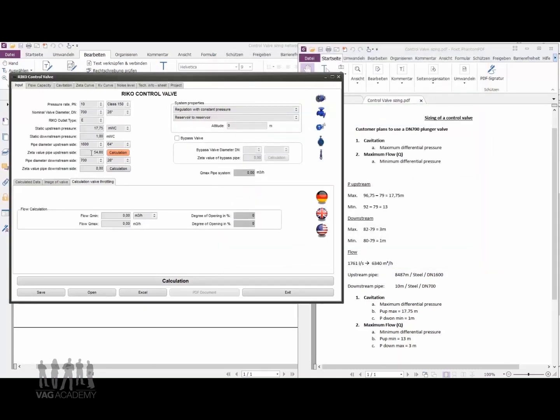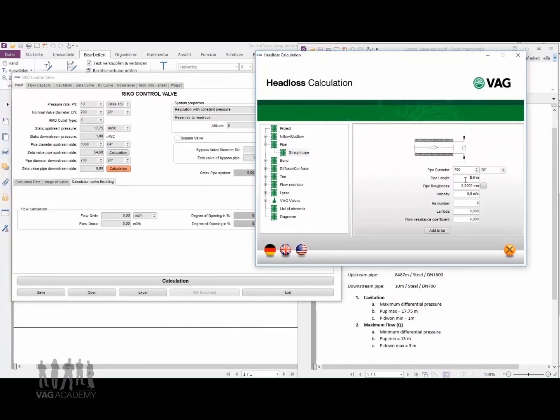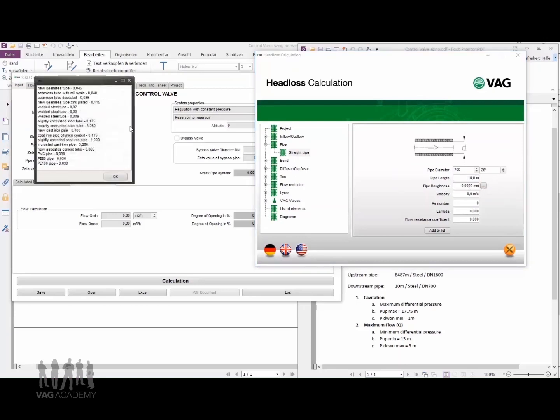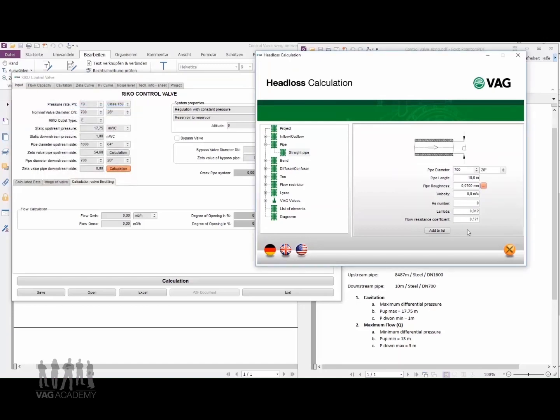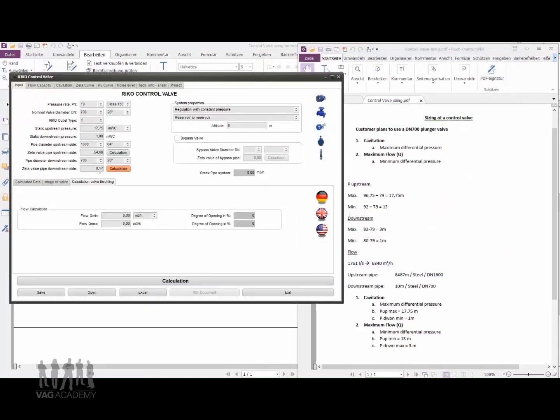I exit and my value of 54.6 is in the field. I do the same for the downstream — a pipe only 10 meters long, same material. I add the flow resistance coefficient to my list. You can add multiple ones and keep adding to the list, and as you exit, all values are added. I can also enter my minimum flow requirement — I don't have that so I leave it at 0. My maximum is 6,340 cubic meters per hour. Now I have typed in all the required information for RIKO Control Valve.